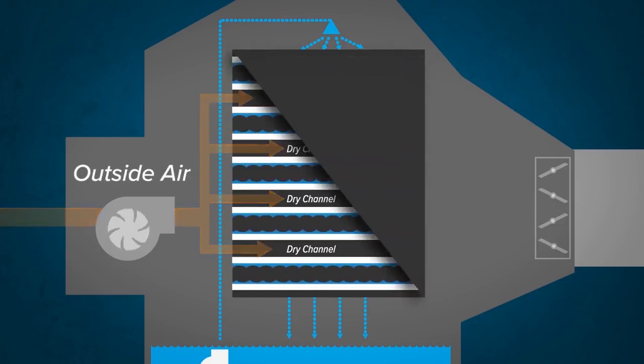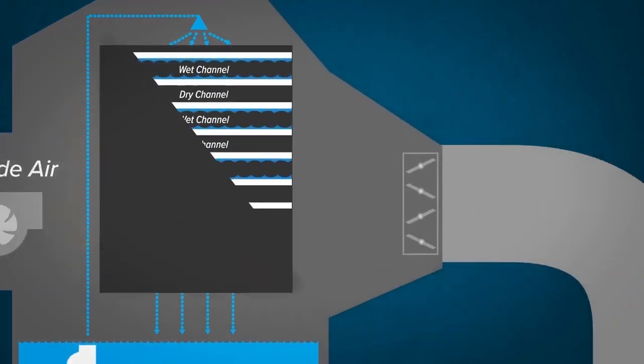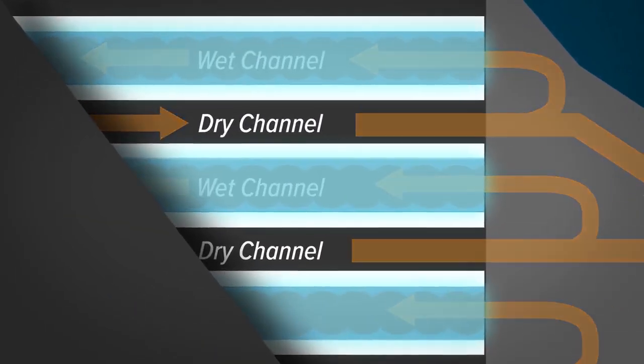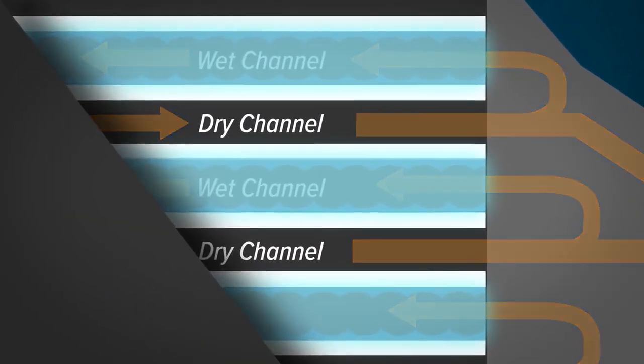Hot outdoor air enters the dry channels of the heat exchanger through a high efficiency fan. After air passes through the dry channels, a portion of the air is supplied to the building and the rest returns through the wet channels. This is where the evaporative cooling process takes place.